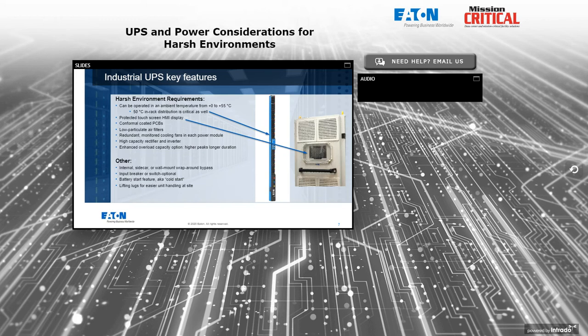And while we're talking about corrosives, we do want to at least make the point that even if you have conformally coated PCBs in the UPS, there are many other electrical connections inside that are still going to be sensitive to corrosive environments. And so you want to pay close attention to the vendor's limits and the application requirements and how much, if any, corrosive gases are present in the air where the UPS will be located.